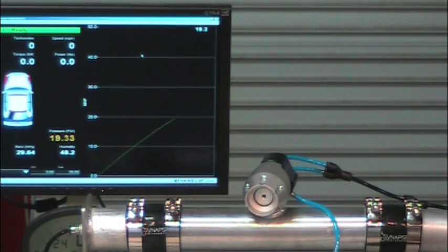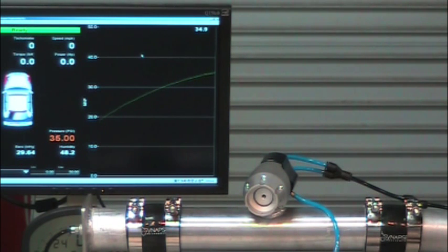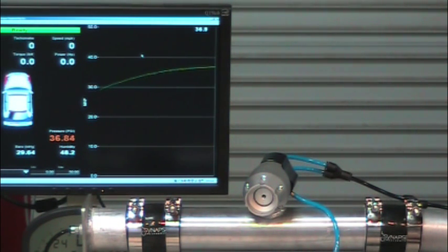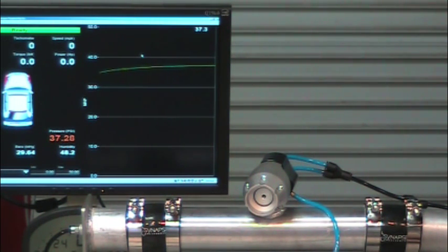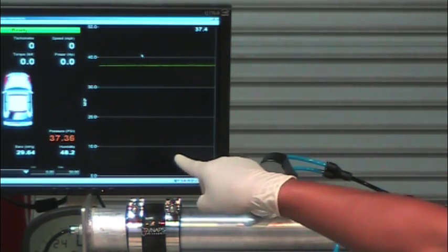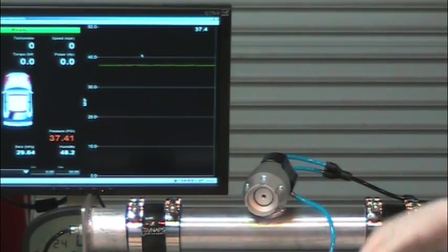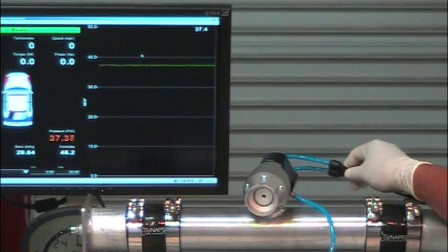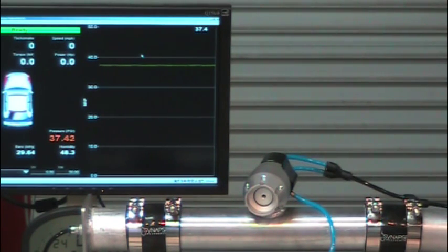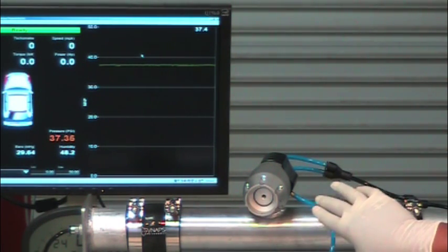So we're going to pressurize this vessel again. And just with the same control pressure. You're seeing 37 psi at the front of the actuator. You're seeing 37 psi at the back of the actuator right now. The valve is staying closed. It's not leaking.